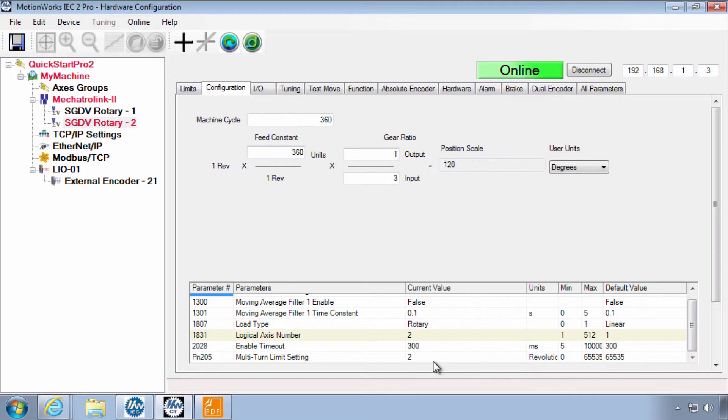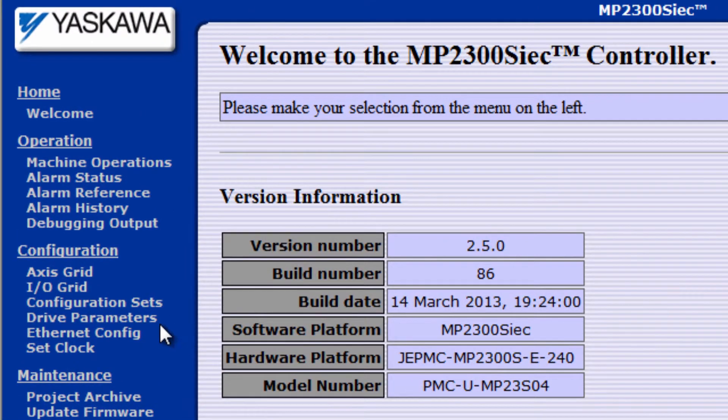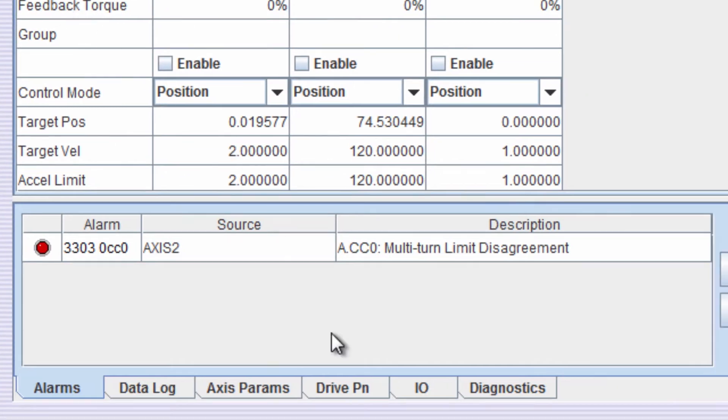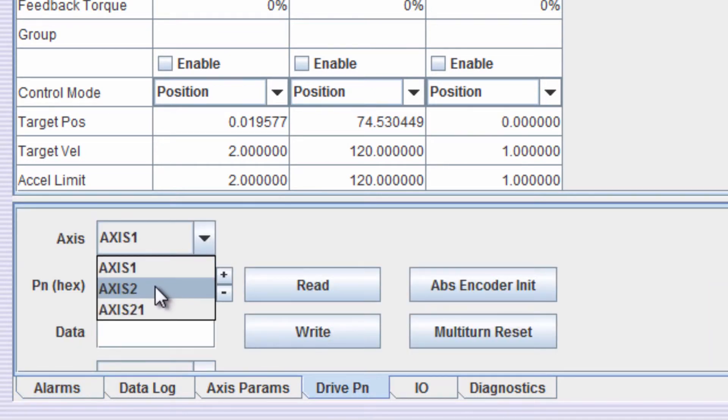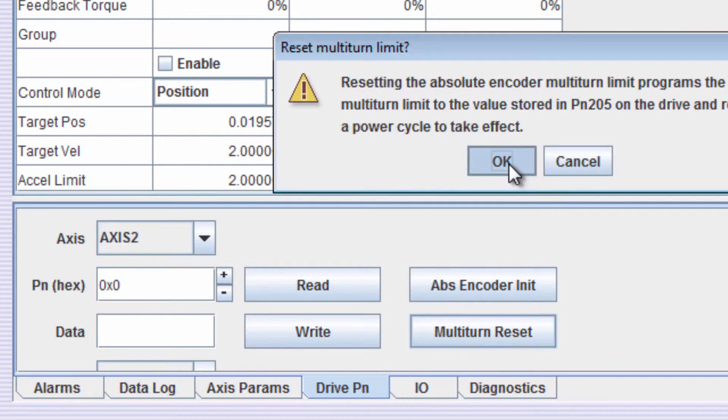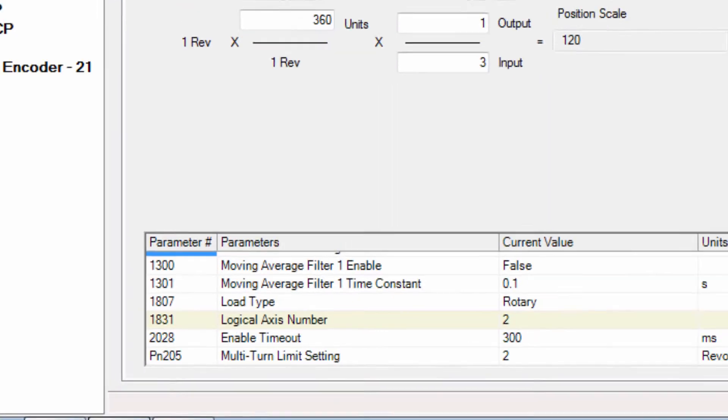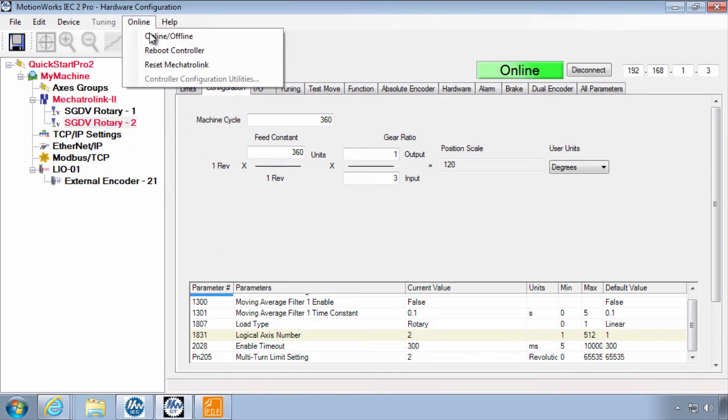So to do that I'll go to the web page. Log in so that I can get to machine operations. Then under the drive PN tab choose the axis that has the alarm ACC0 and perform the multi-turn reset. Click OK and now back in the hardware configuration I'll reboot a second time reboot controller.